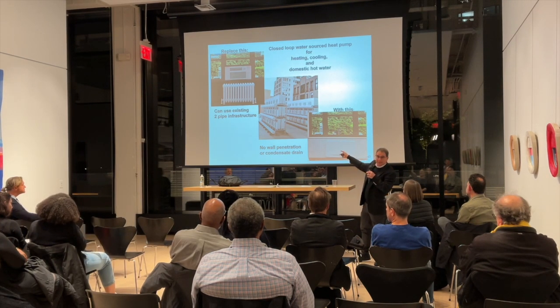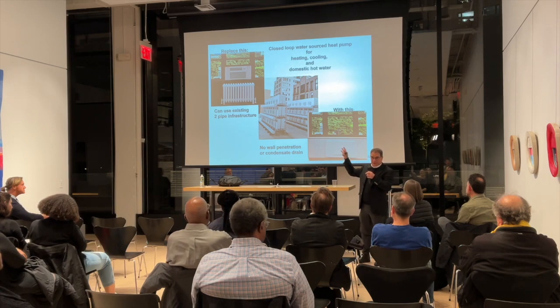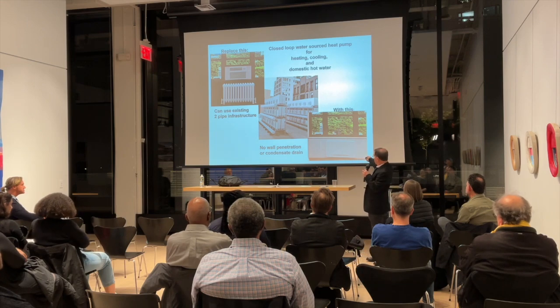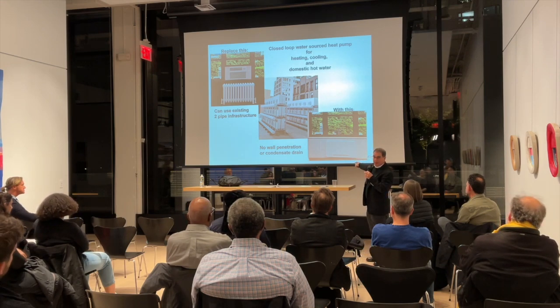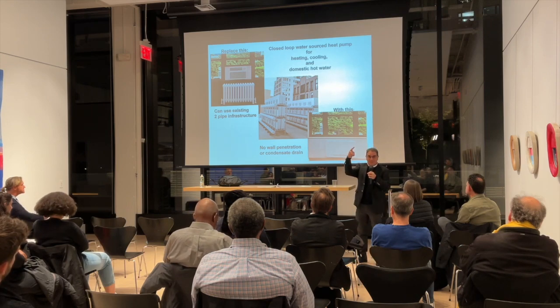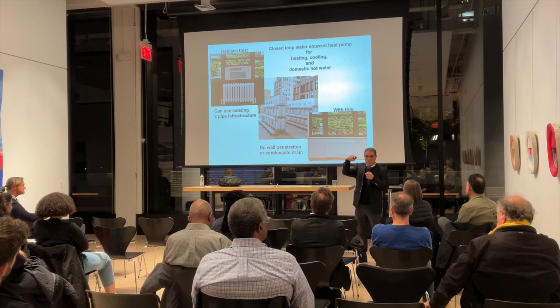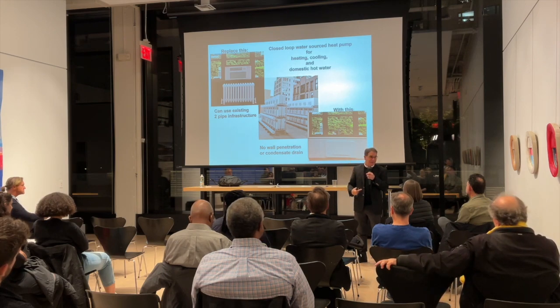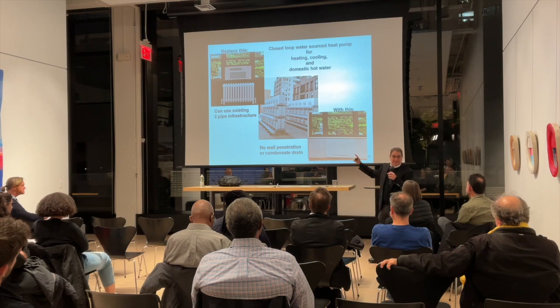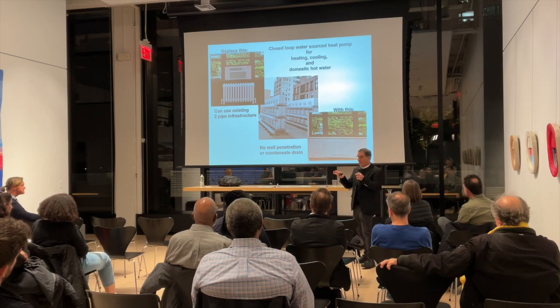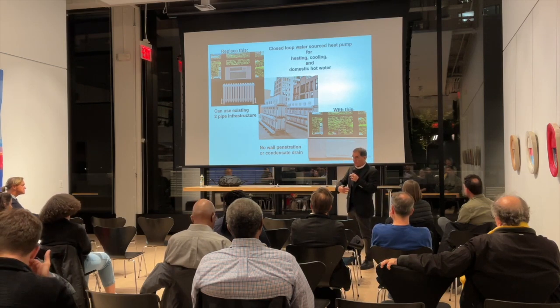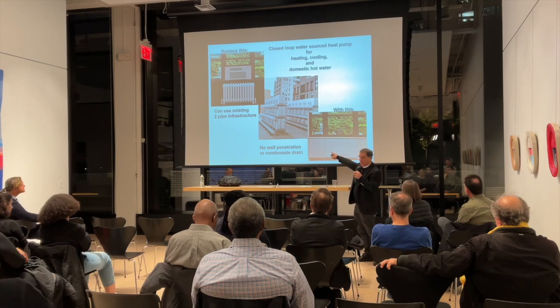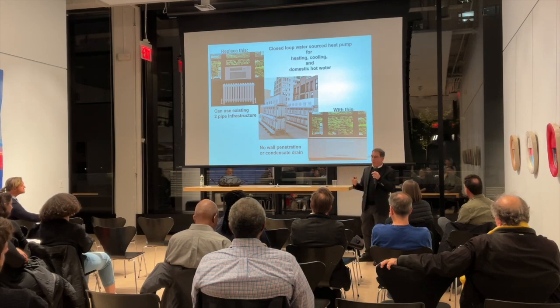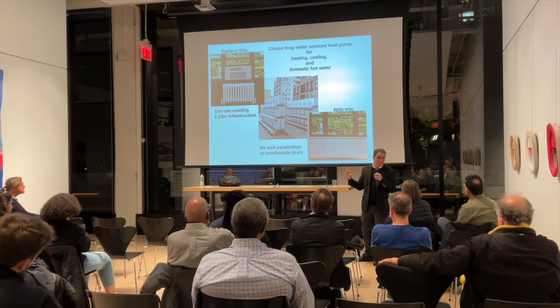What that's doing, as a heat pump, like I showed you in the diagram, is creating 70-degree water. It goes into a 2-pipe system. That 2-pipe system is feeding into that unit over there. That unit then either heats the water up to 80 or 85 degrees or cools it down. And you get air conditioning and heating at a very inexpensive change in the delta of that water. And now you have no chemicals running through your building. All you have is a water system. And that same unit can also be fed into a boiler that will provide domestic hot water. So this does all three.